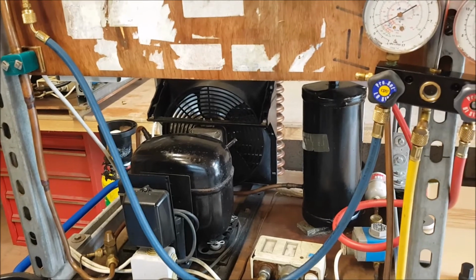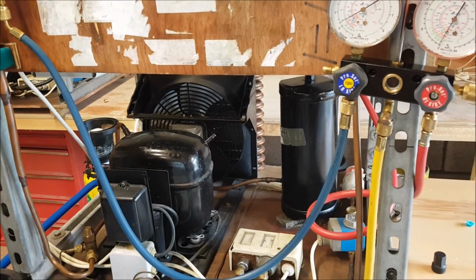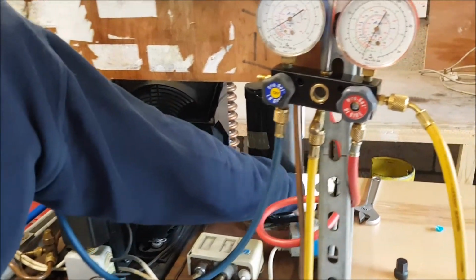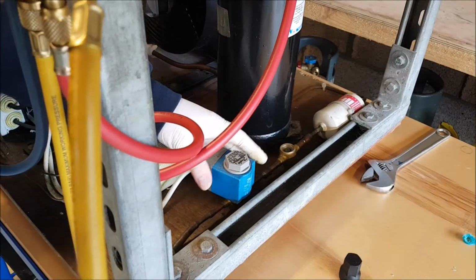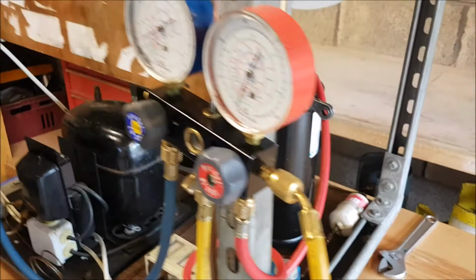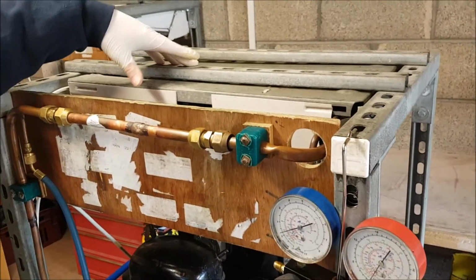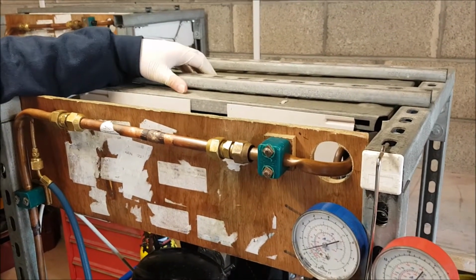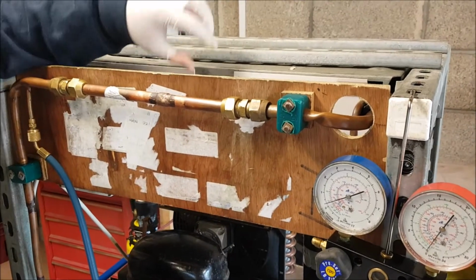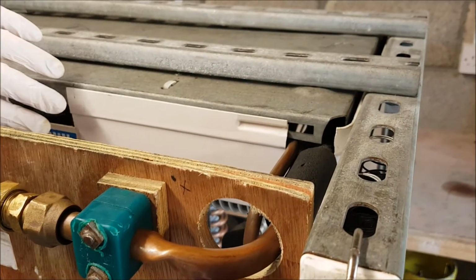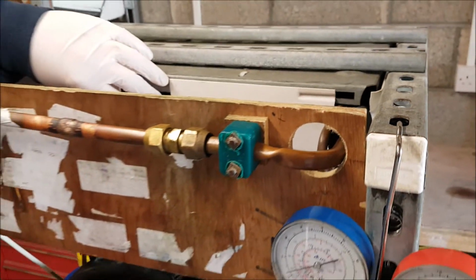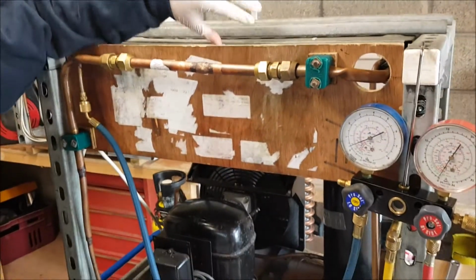That means that once we pump the refrigerant down to the high side of the system, we will be able to work on changing our filter dryer, changing our sight glass, changing or opening our solenoid, taking our evaporator away and putting a new one in place, for example, carrying out any kind of remedial work that's needed. And the thermostatic expansion valve located inside this actual evaporator, we could take that apart. We can change the orifice on it, we can change out the valve and so on.